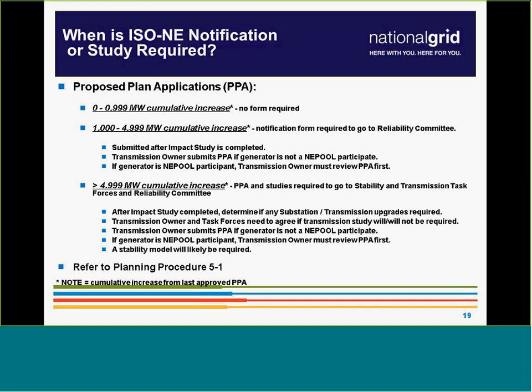Didn't want to get into some of these issues related to all the solar that's gone in. We now have 800 megawatts or so connected to our system in Massachusetts. We have about a 5 gigawatt peak load on a hot summer day. On Memorial Day weekend with no air conditioning and no heat load, our load is only about 2,500 megawatts. But you still have the 800 megawatts of solar pumping out full blast at 1 o'clock in the afternoon on Memorial Day weekend, with nice cool weather and good sun.